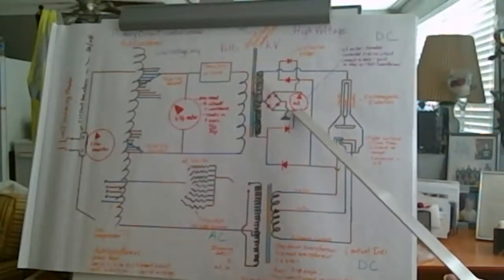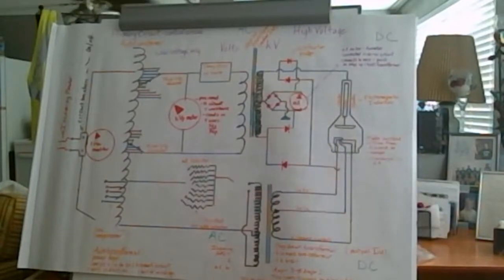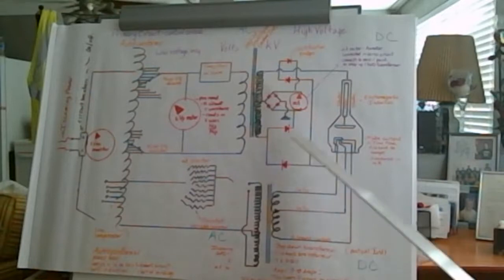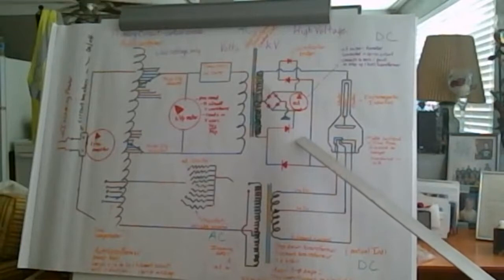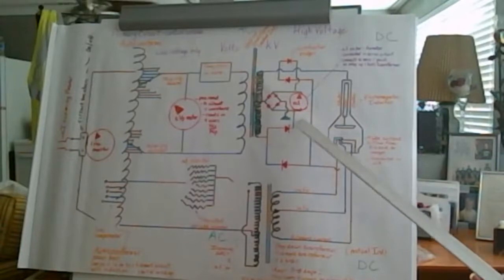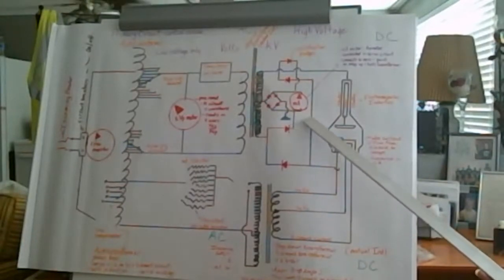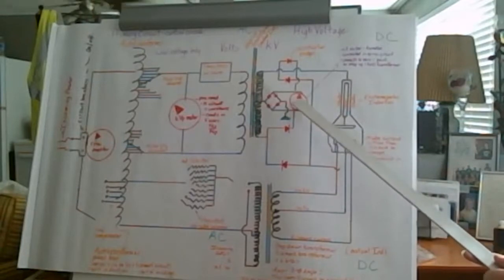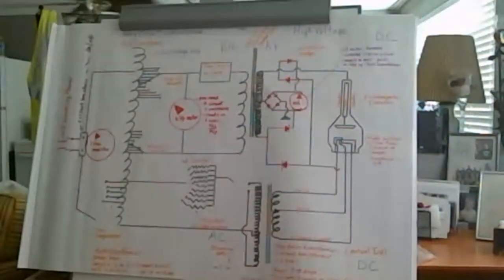although it's being measured over here on the high voltage side, we actually have an mA meter that appears on our control console, right? And if you ever paid attention to it when you were making exposures in that room, at the very moment of exposure is when you get that information from that mA meter to your control console.